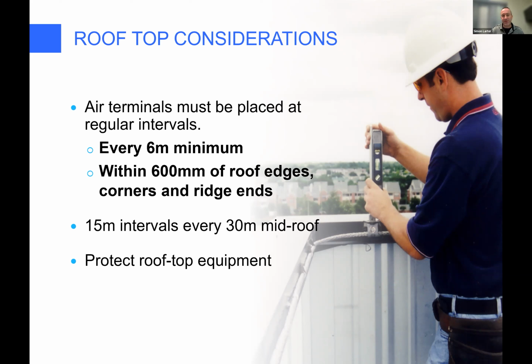So you drive from here down to Montana, you cross the border, and all of a sudden lightning protection looks completely different. We didn't have to have lightning rods in Canada from 1987 to 2020 because all you needed to do was run a conductor on top of a parapet and call that the strike point. Well, that's not nearly as good for counter leader development as a lightning rod is. It's not even how they do it internationally in Europe anymore. So we needed to update our code, so we did.